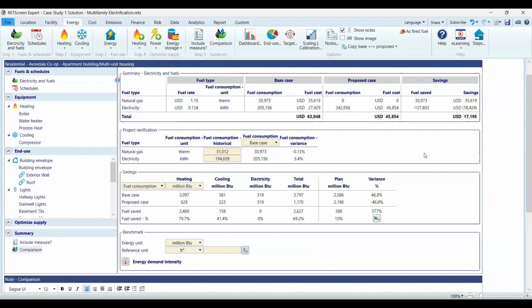But these two measures don't have any interactive effects between them. Meaning, when I replace my boiler with heat pumps, let's say I end up saving 100 units of energy. And if I replace the domestic hot water with a heat pump water heater, I end up saving 50 units of energy. I can simply add those two and confidently say that the total savings would be 100 plus 50, because there are no interactive effects between them. So that would answer your final question. Are there any interactive effects? No. These two measures do not interact with each other. Any questions for the first case study? All right. Let's go to the second one.